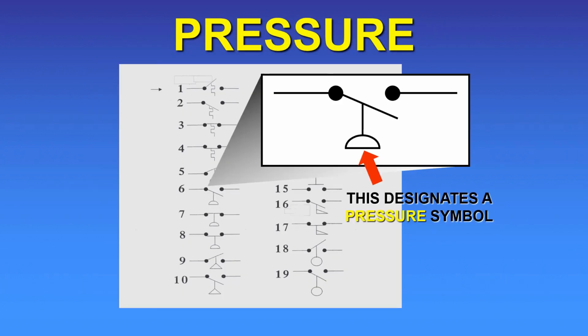There are many kinds of symbols that are used in wiring diagrams, and let's just look at a couple to familiarize you with the types of symbols that are used in wiring diagrams. This one is a pressure switch, and this designates a pressure symbol. This also shows you that this pressure switch will close on pressure rise because the line is below the dot on the right-hand side. So when the pressure rises in the system, this switch will close and make the electrical circuit.